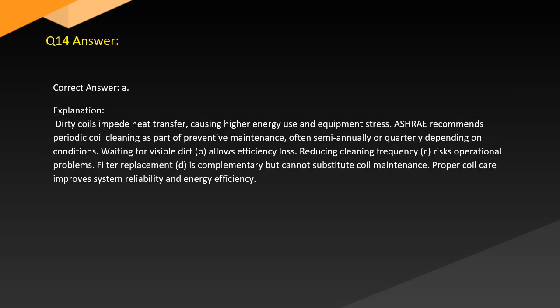Answer. Correct answer: A. Explanation: Dirty coils impede heat transfer, causing higher energy use and equipment stress. ASHRAE recommends periodic coil cleaning as part of preventive maintenance, often semi-annually or quarterly depending on conditions. Waiting for visible dirt, B, allows efficiency loss. Reducing cleaning frequency, C, risks operational problems. Filter replacement, D, is complementary but cannot substitute coil maintenance. Proper coil care improves system reliability and energy efficiency.